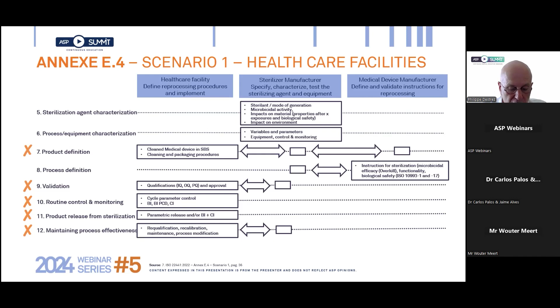So with this slide, we are in sterilizer manufacturer domain, and it corresponds to the early development stages where the manufacturer evaluates the microbial efficacy. Can you click? It also evaluates the effect of the process of the sterilizing agent on material, including the biological safety aspect, that is to say, the risk of having toxic residues appearing on the surface of the medical device. And the last point, if you want to click again, is related to the safety of the operator. We'll now go to the following slide, number 6.